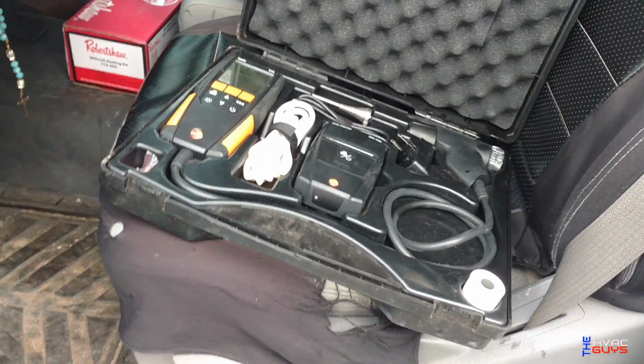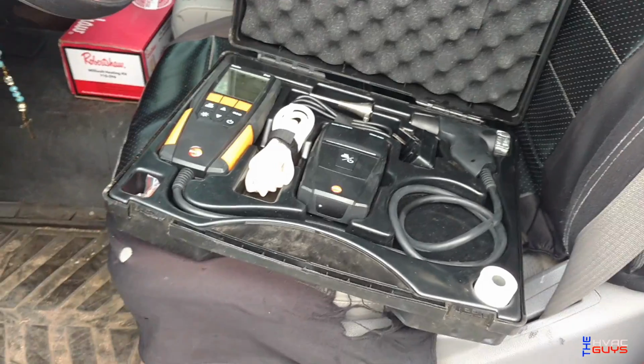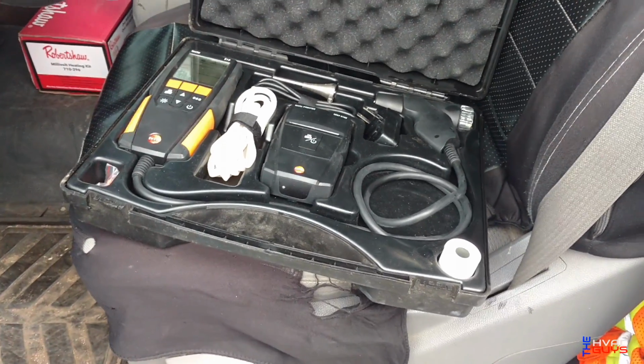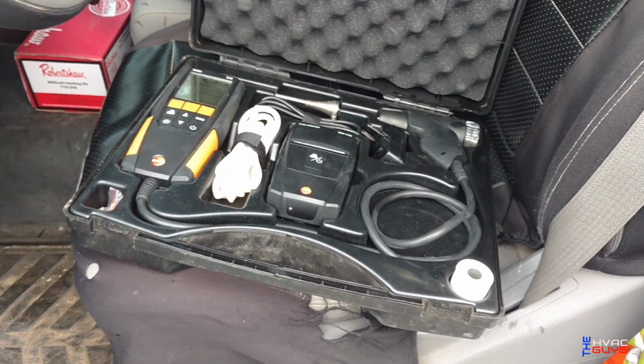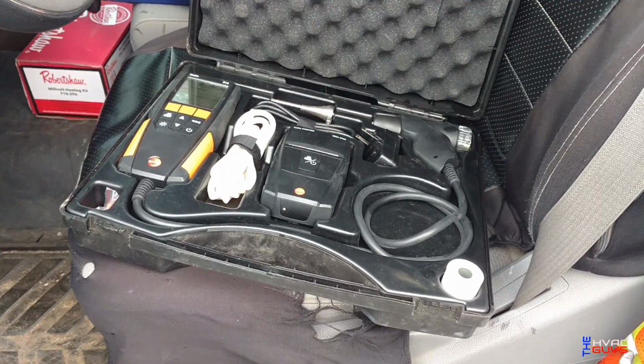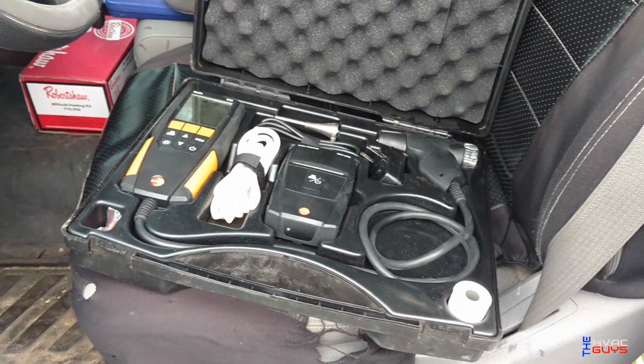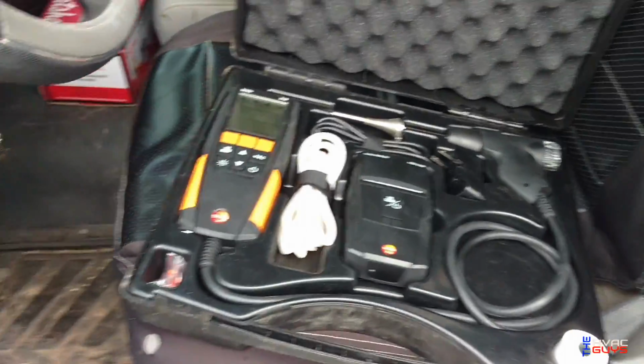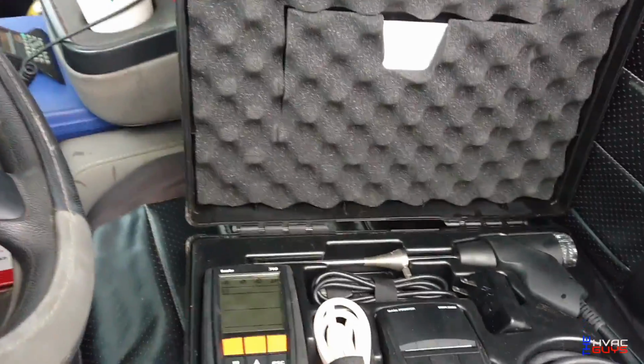So then we hooked up our combustion analyzer and tested the ambient CO inside of the home, and it was going up to 10, which is the maximum recommended amount. But for me, I don't want to take that risk anyway at 10, so we condemned that furnace.